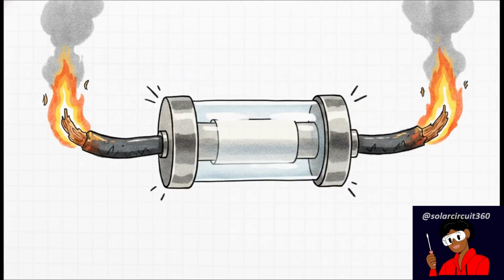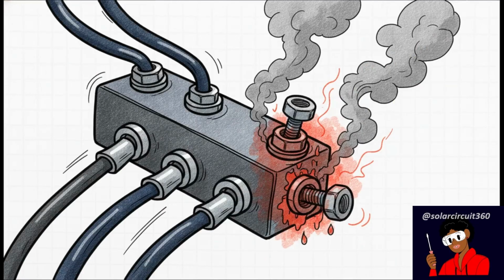And then there are fuses. This is a massive blind spot for so many builds. A lot of people honestly just guess what size fuse they need. But listen, a fuse is totally useless if its rating is higher than what the cable itself can handle. The golden rule here is that a fuse must protect the cable conductor, period. If your wire maxes out at 150 amps, but you just slap a 250 amp fuse on it, the wire will literally melt its own insulation and burn up while the fuse just sits there intact, completely unaware there's even a problem.